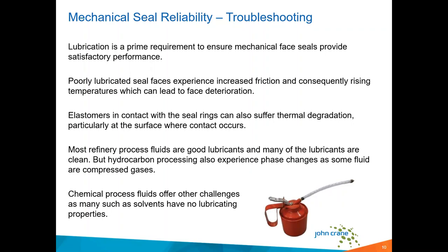So one of the main factors that influences mechanical seal reliability is lubrication. It's no secret that all seals will leak. All seals leak because they need fluid at the faces for lubrication. Some mechanical seal designs operate as dry seals with a gas barrier. But in that case, they're using specialized face technology to be lubricated with a gas film instead of a liquid, but still lubrication is required.